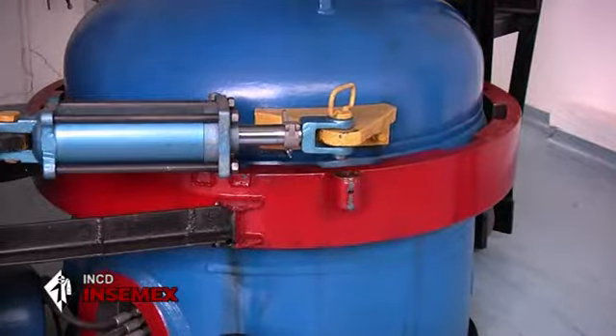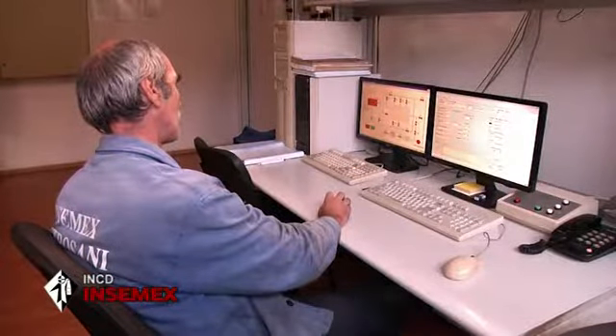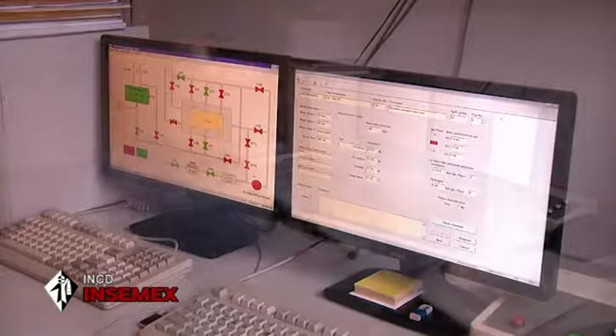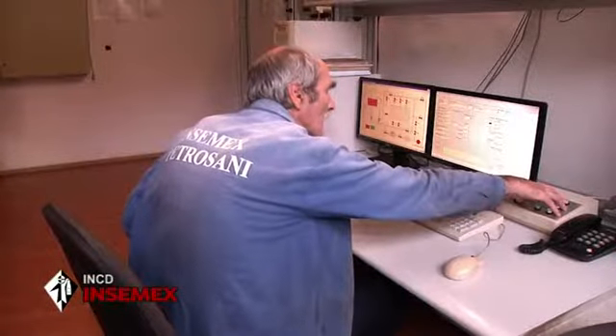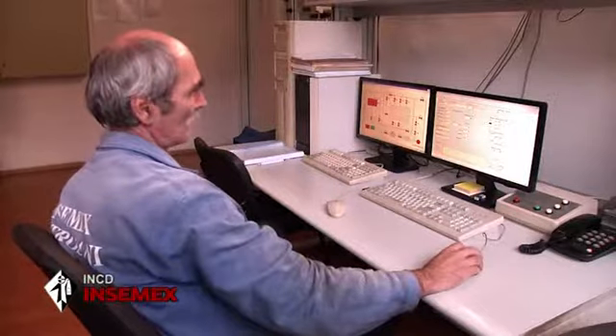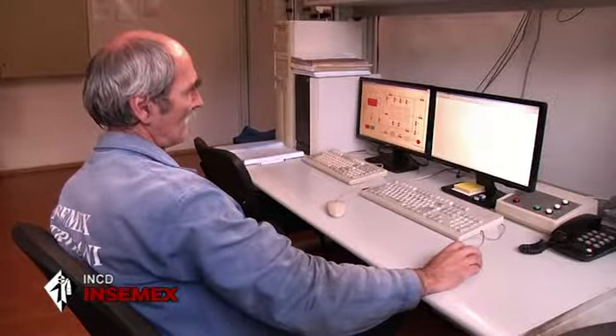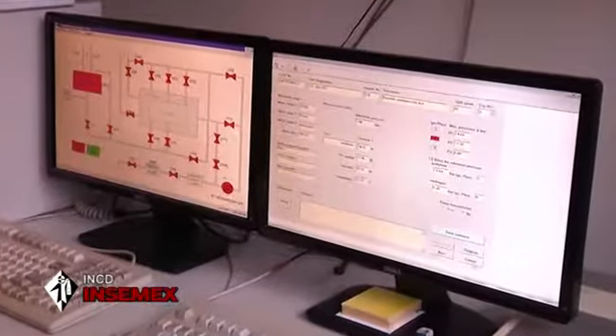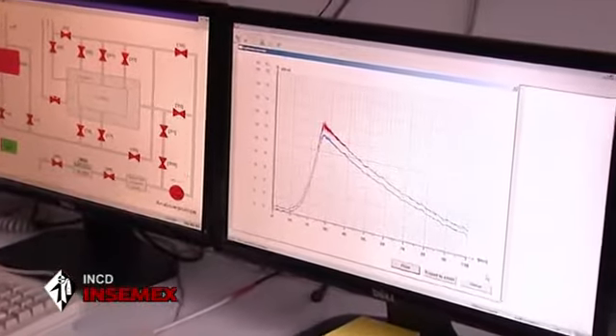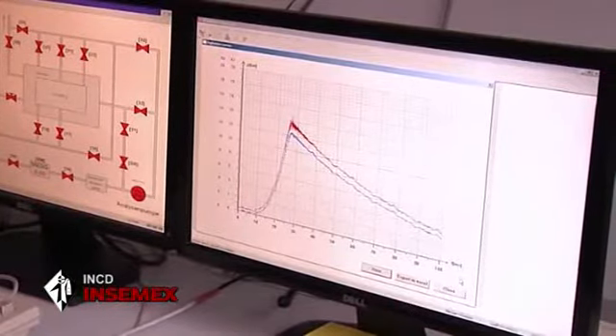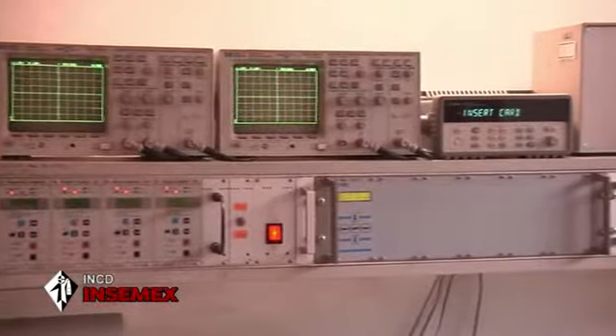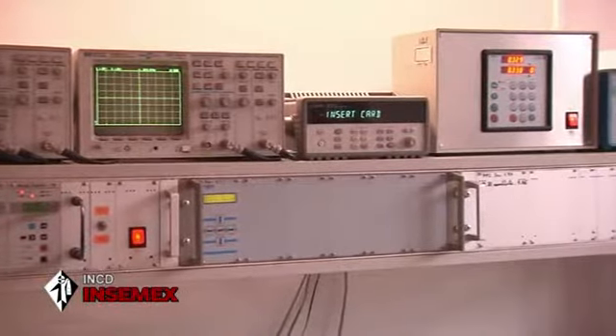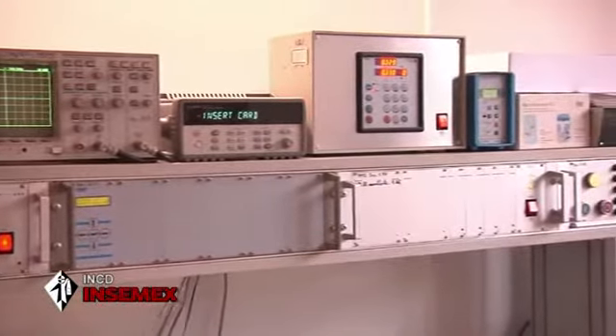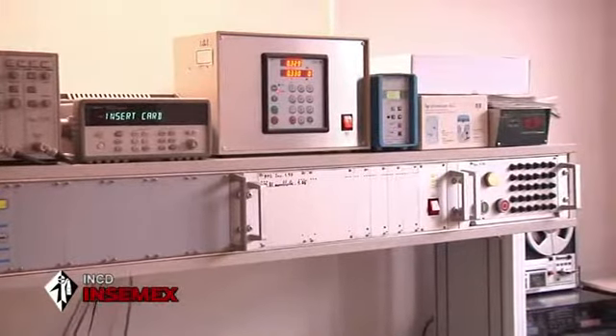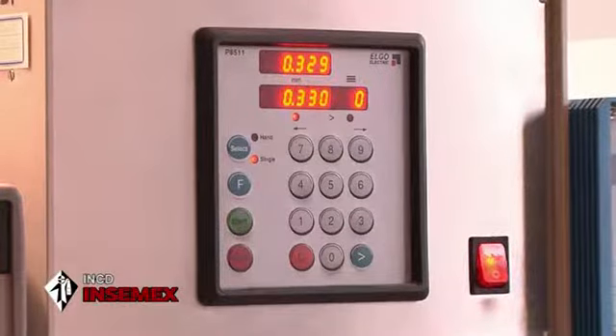The stand is used for performing tests in explosive mixtures in accordance with the requirements of the European Standard 60079 Part 1, being used for performing the following tests. Test for determining the maximum explosion pressure, reference pressure, through which there is determined the maximum explosion pressure. Overpressure test, through which there is tested the capacity of enclosure to withstand to overpressure. Test for non-transmission of an internal ignition, through which there is tested the capacity of the equipment's enclosure not to transmit an internal explosion to the explosive mixture from outside the enclosure.